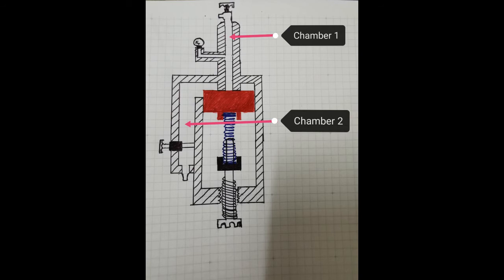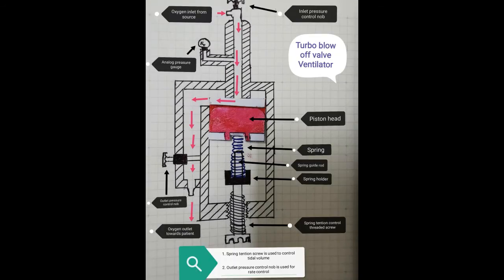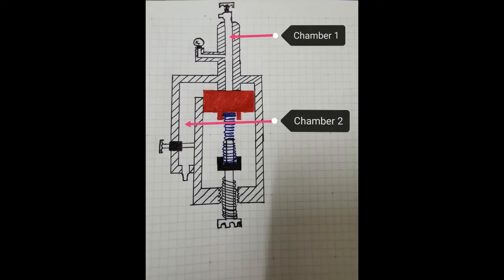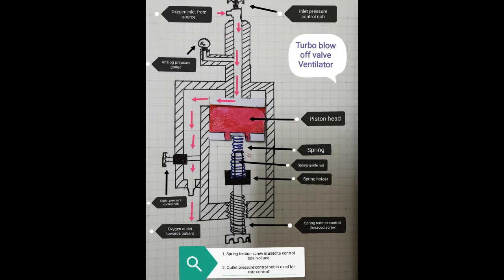With time, the pressure inside this chamber 1 increases and starts to push the piston down. And when the pressure inside chamber 1 is greater than the spring tension behind the piston, the valve eventually opens and the compressed air gets into the next chamber, which is chamber 2. And when the pressure inside chamber 1 falls below the tension of the spring, the piston automatically closes chamber 1. This allows the pressure inside chamber 1 to build up again. During this time, the air expanded into chamber 2 will find its way through the exit port at the rate which we set on the outlet pressure control knob. This process will then be running continuously. I hope this helps in any way to build an emergency ventilator.